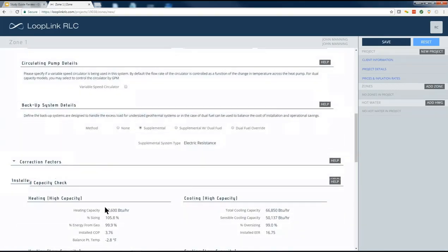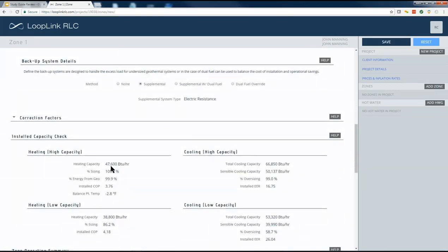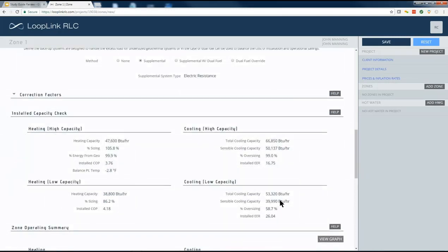And notice that as I scroll down here on the page, that 5-ton unit gives me the 47,600. So about 4 tons of actual heating capacity in heating mode with a 30-degree loop. But take a look in terms of our percent sizing relative to the peak heating load. We're 105% sized. We're getting basically 100% of the energy from the Geo unit, not relying on supplemental resistance heat at all.